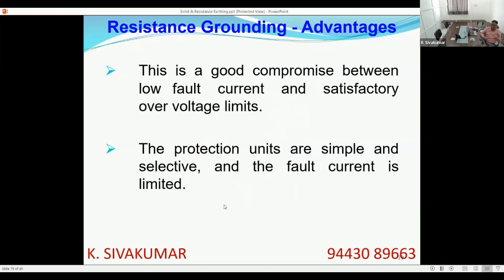The other day we saw what happens if the earth fault loop circuit is resistive. The maximum voltage that can appear in such a case is root 2 V. However, the system is designed for tolerating a peak voltage of root 2 V. So there is no transient over voltage. So it is a very good compromise between a solidly grounded system and a totally ungrounded system. The protection units are simple and selective. Fault current is limited.